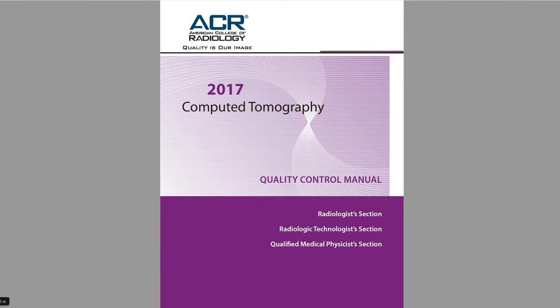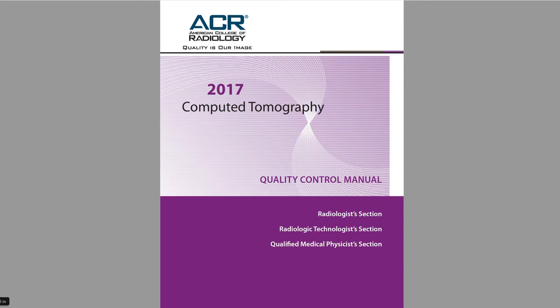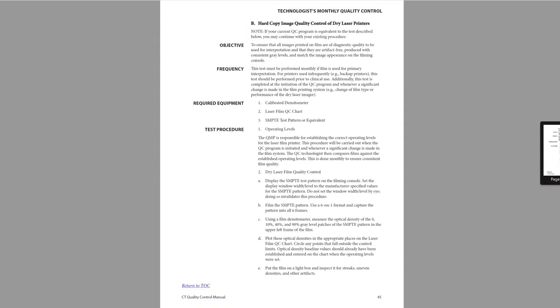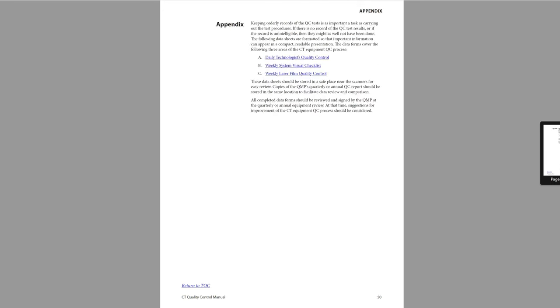So let's go ahead and take a look at a couple documents and figure out where we can find out a little bit more information about a SMPTE pattern and how we evaluate this SMPTE pattern. So the first thing that I want to show you here is the ACR CT quality control manual. This is, as of this recording, the most recent from 2017.